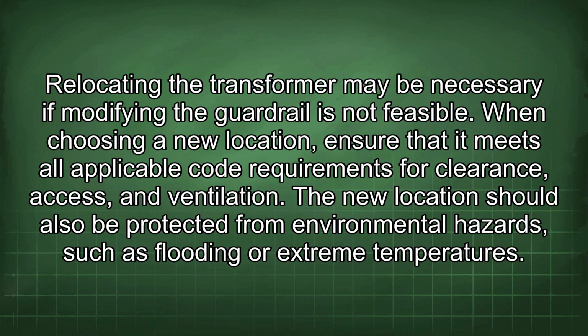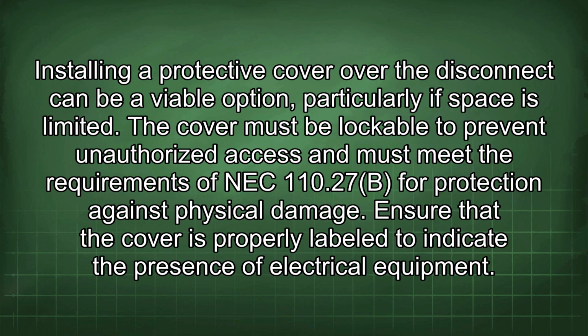Relocating the transformer may be necessary if modifying the guardrail is not feasible. When choosing a new location, ensure that it meets all applicable code requirements for clearance, access, and ventilation. The new location should also be protected from environmental hazards such as flooding or extreme temperatures. Installing a protective cover over the disconnect can be a viable option, particularly if space is limited. The cover must be lockable to prevent unauthorized access and must meet the requirements of NEC 110.27(B) for protection against physical damage. Ensure that the cover is properly labeled to indicate the presence of electrical equipment.